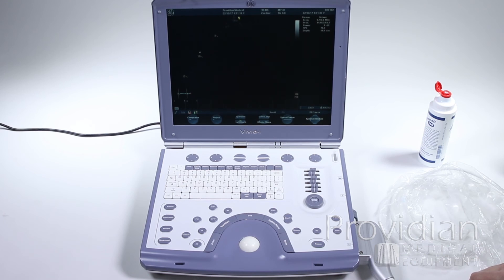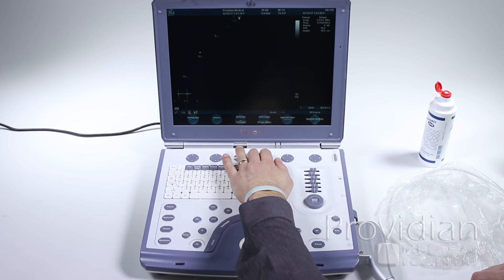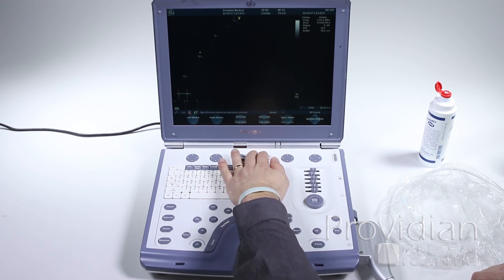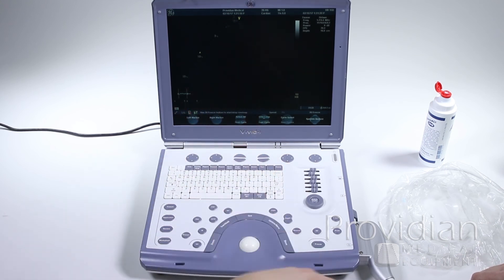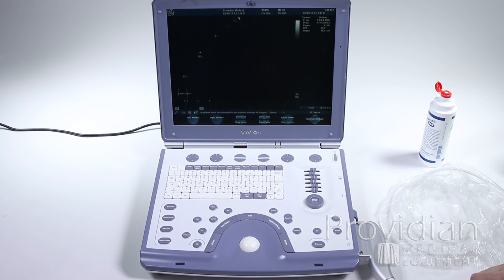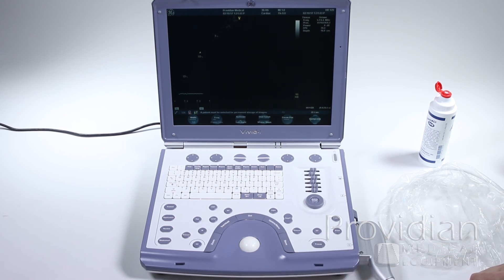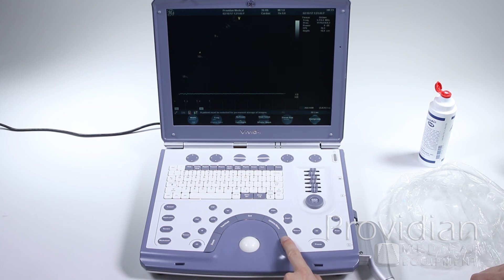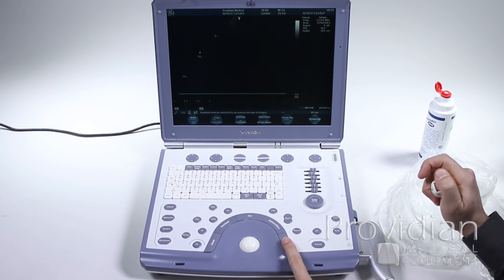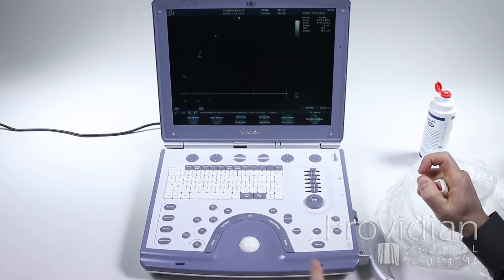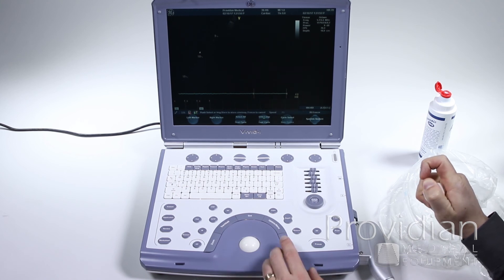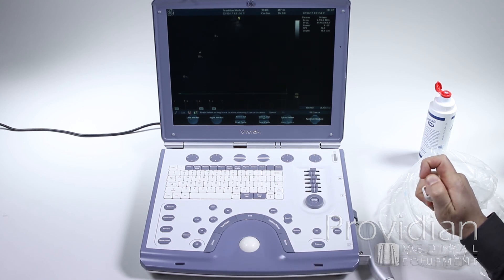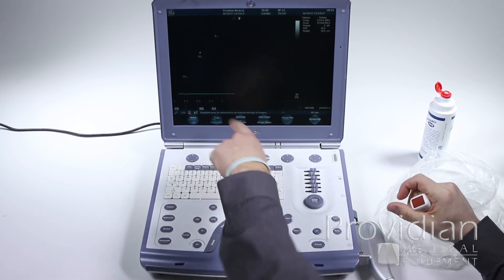Now that probably sounds kind of odd, but if you want to store a single image, just hit the freeze key and then hit store. If you want to save a loop, you either have to play the cine loop, pressing here, and actually have it play. While it's playing, you hit store, then it will save the loop. Or you can also save a cine loop by pressing the store key in a live imaging mode. Without hitting freeze, I can hit store, and then store again, and then it will save my loop.